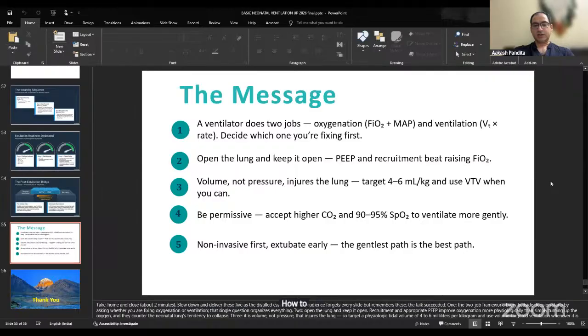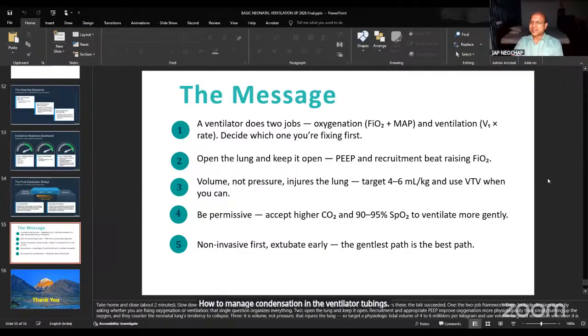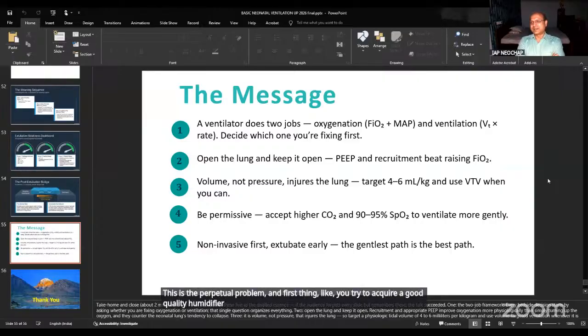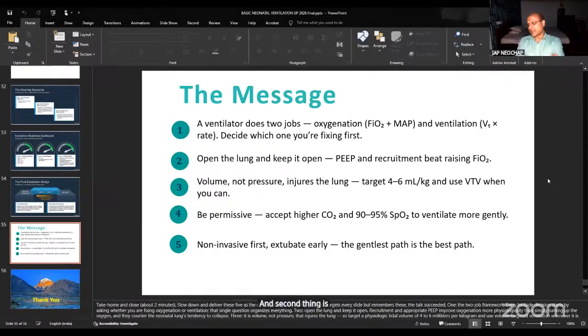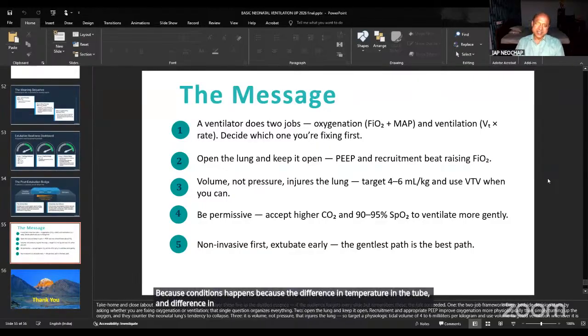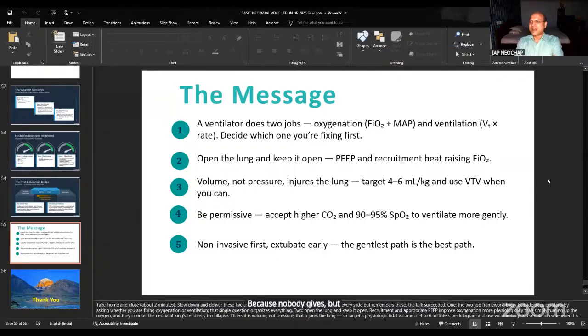How to manage condensation in the ventilator tubings? This is the perpetual problem. First thing, try to acquire a good quality humidifier. That is one thing I have learned over the years. And second thing is your temperature in an ICU should not be very low, because condensation happens because of the difference in temperature in the tube and the environmental temperature. If the ICU temperature is 20, 22, a lot of condensation will happen. Nobody keeps it like that, but sometimes by mistake you can have these problems.